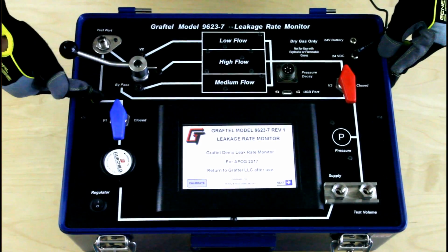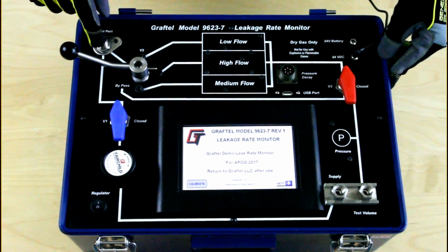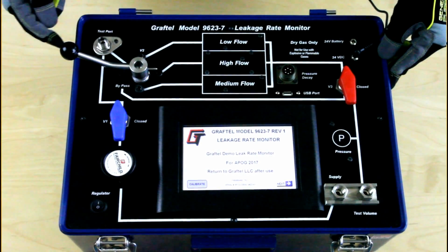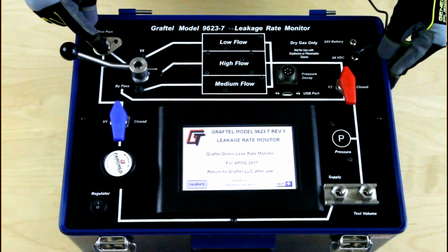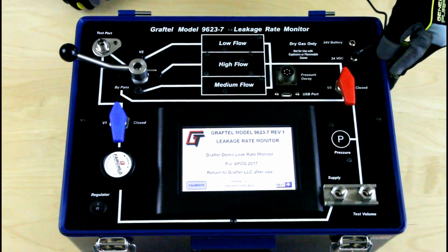The next stop is the calibration port. This port should always be capped, and only accessed during the calibration process or when an external regulator will be used.